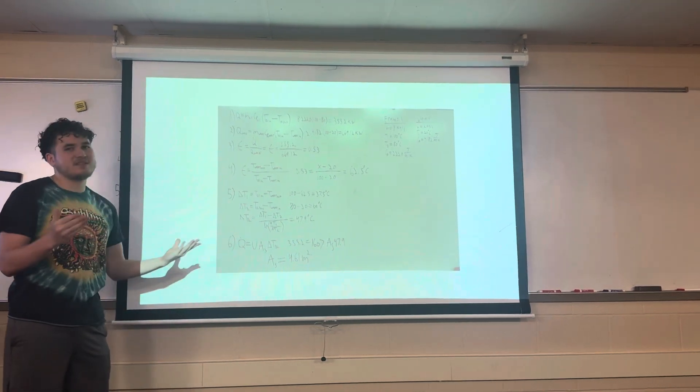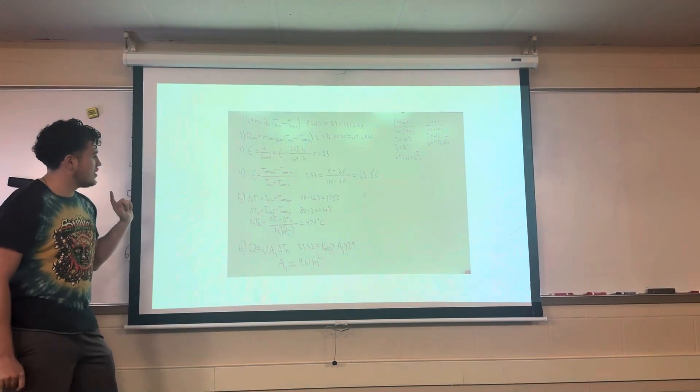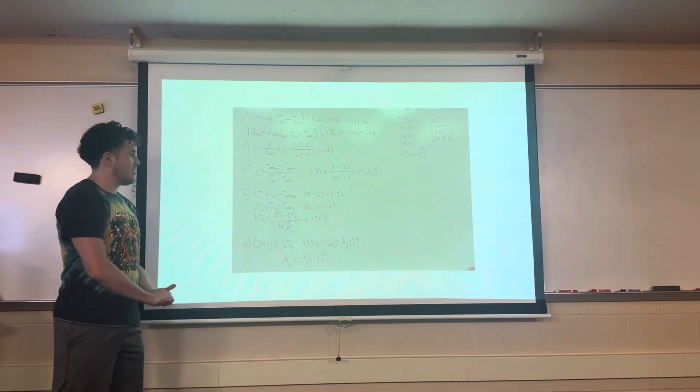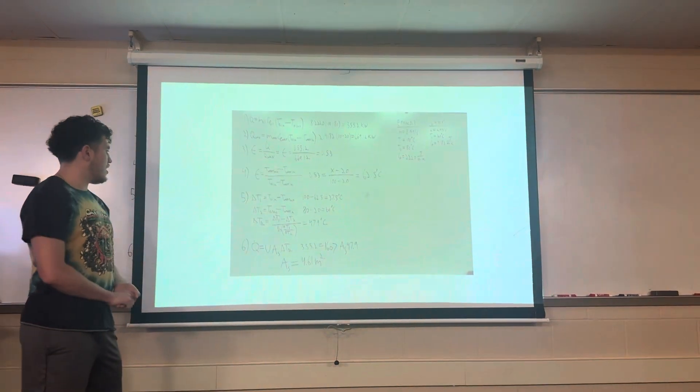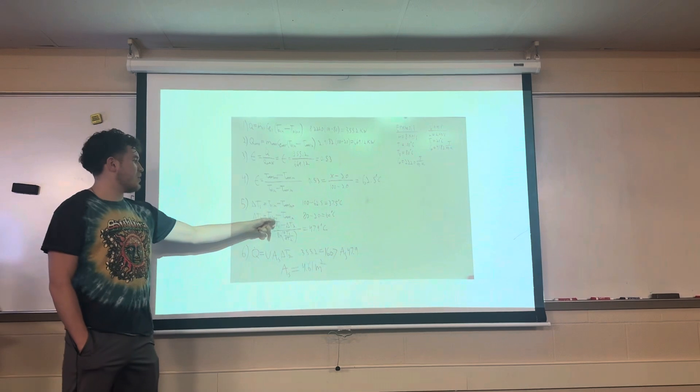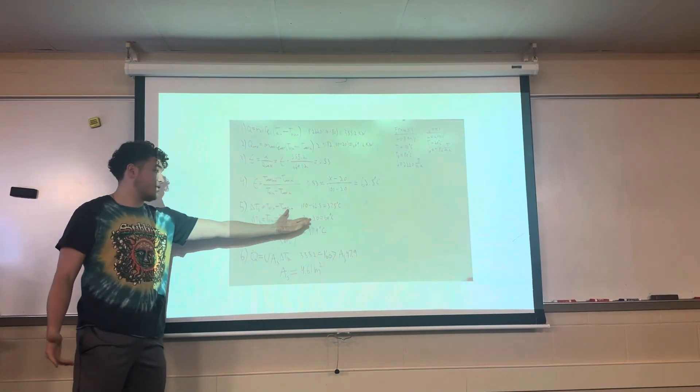The way I solve the system, I use the log mean temperature difference. Our first delta T1 is oil in minus water out. That ended up with 37.5 degrees Celsius. Our second was the oil out minus water in. That ends up with 60 degrees Celsius.